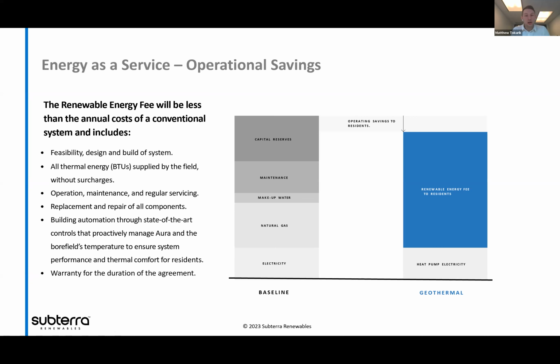But the full picture also includes the other operating costs, which are the maintenance to otherwise maintain those pieces of equipment, and the capital reserve. You know that your chiller is going to break down in 15 or 20 years, and it's going to cost $1 million to replace. So over those 15 years, a prudent asset manager is putting away $1 million divided by 15 plus some escalation, so they don't have to cough up or find that $1 million - they've already got it saved. That's the capital reserves.